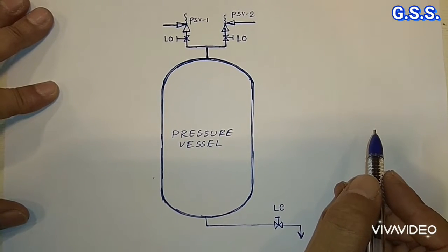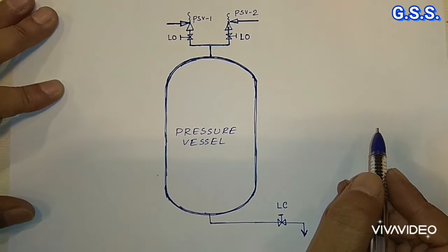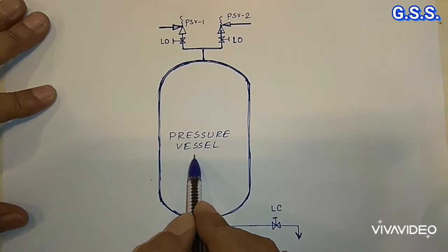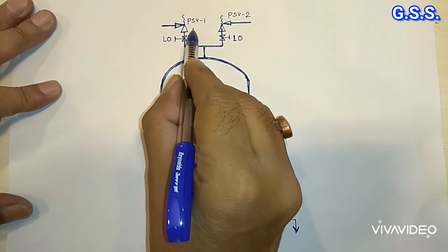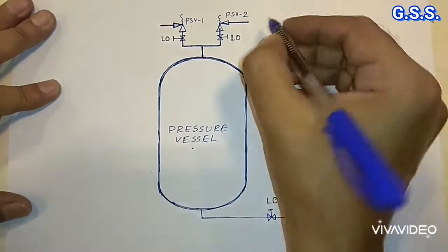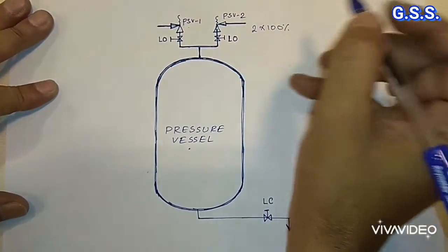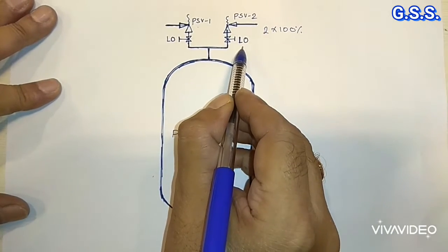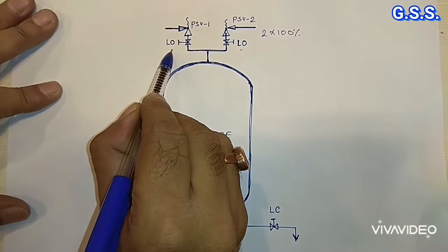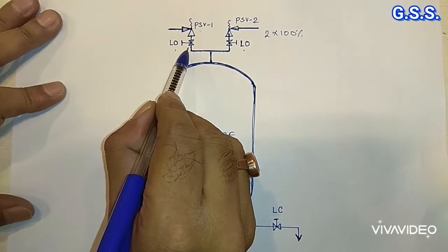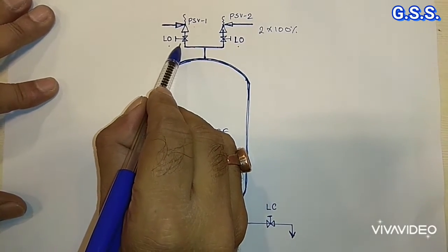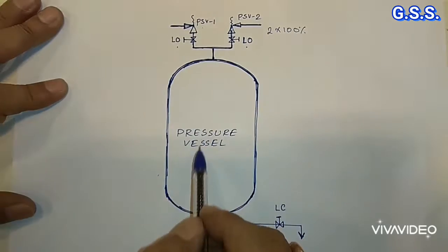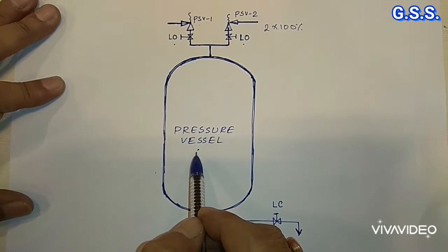Now let us see why locking devices are required for valves. Suppose this is one pressure vessel and every pressure vessel should have two safety valves — 2 into 100% safety valves. The inlet isolation valve of the safety valve should be locked open type, so that nobody will be able to close the isolation valve. If anybody closes the isolation valve, the safety valve will not work and it will be a safety issue.